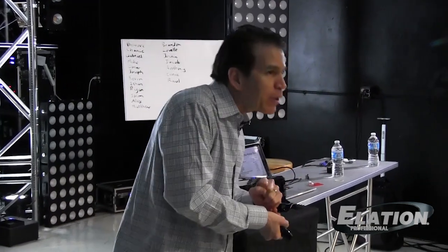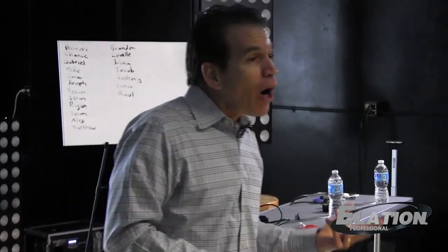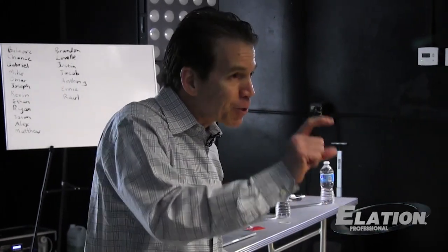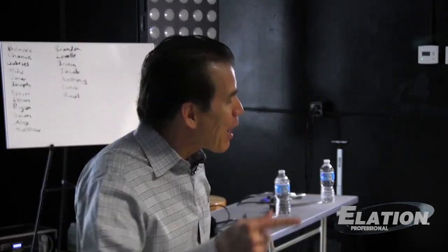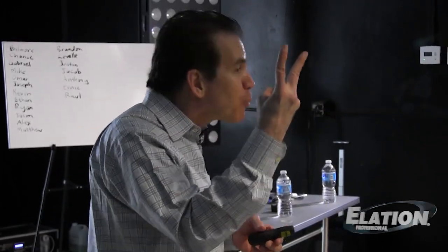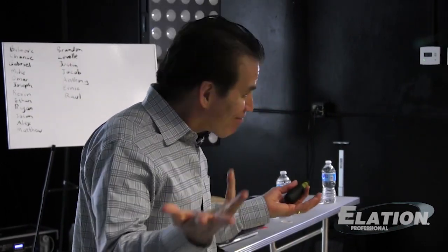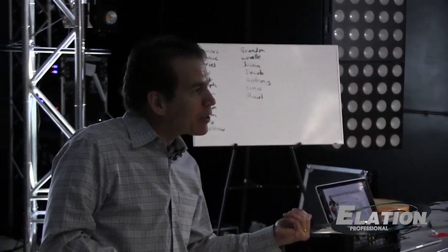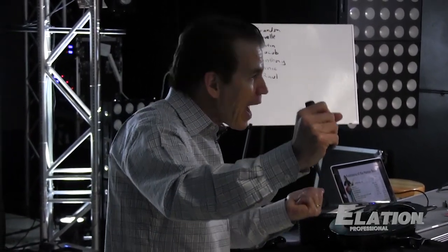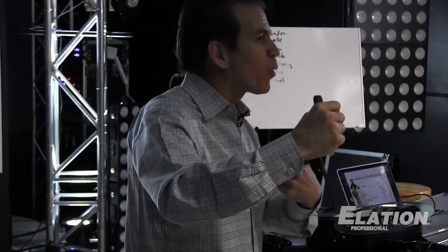But if the green wire is broken, or if it's not there because the audio engineer lifted the ground, have you ever seen those ground lift adapters? You know what I'm talking about? When you get a ground loop, you take a 3-prong connector from the amplifier, you plug it into the adapter, so now it has 2 prongs. What's that third prong? It's the green grounding conductor. And if it's not connected, if there's a fault, now the amplifier is at line voltage, at 120 volts. It's got nowhere to go until somebody touches the guitar strings and then touches the microphone. And now you've connected the circuit through your heart. And that's how people die.